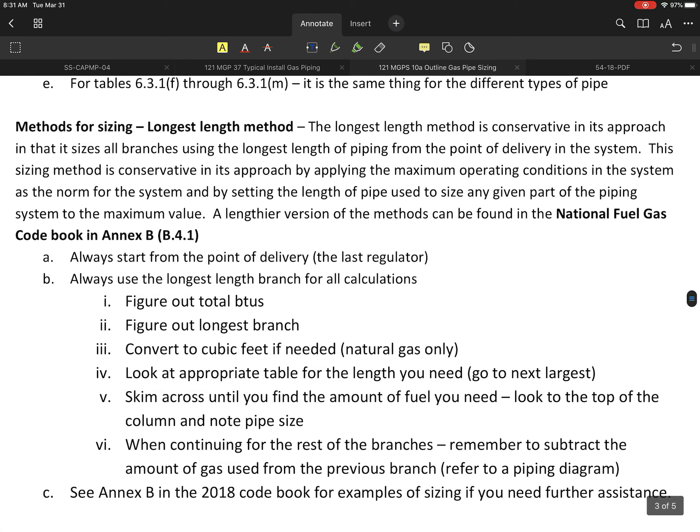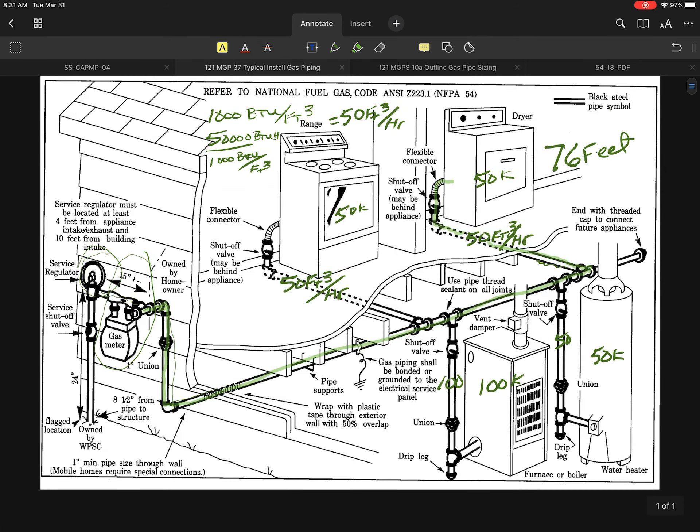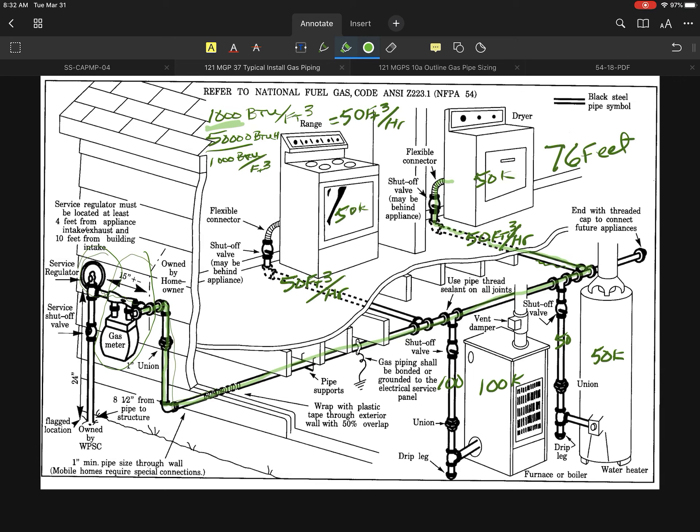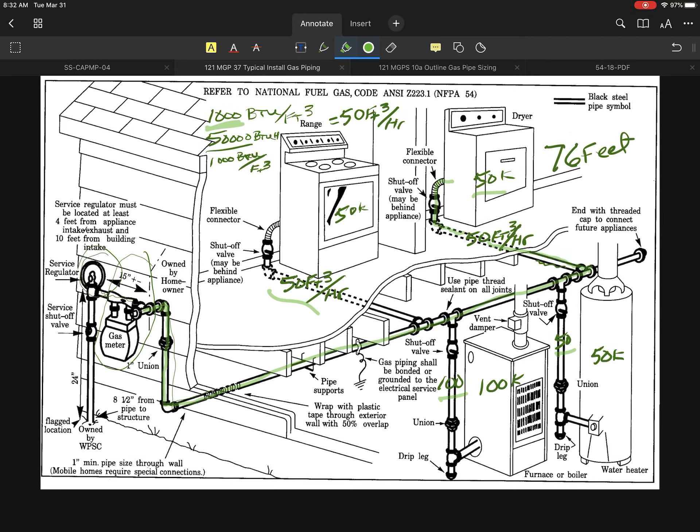I'll need to figure out my total BTUs. The total volume of fuel that I need is essentially going to be, since I'm going to use the basic 1000 BTUs per cubic foot, and each one of these I figured out the volume: 50 cubic feet, 100 cubic feet, another 50 here and another 50 here. So for these four appliances, that's 100, 150, 200, 250. That means I'm going to be having to move through this system 250 cubic feet per hour of fuel.